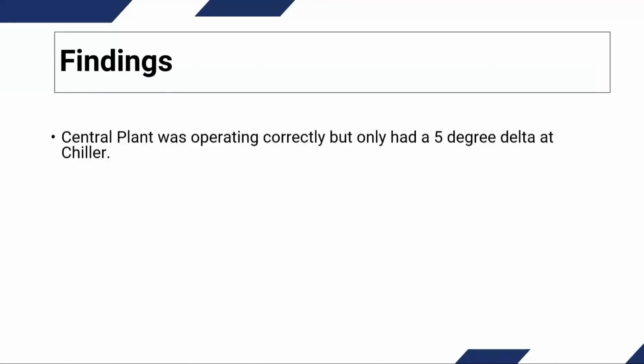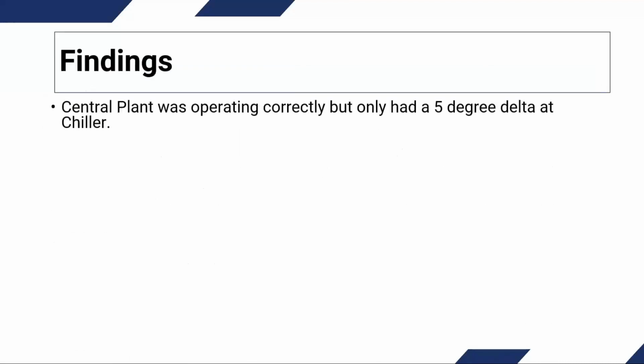So what we found on this building was the central plant seemed to be working pretty good. We had correct flows at the chillers. Chillers were performing. The one thing that we did notice was that there was only a 5-degree delta at the chiller. We really were expecting to see about a 12-degree delta if everything was working correctly. When we have a low delta like that, it typically indicates to us that we have an unbalanced water system.